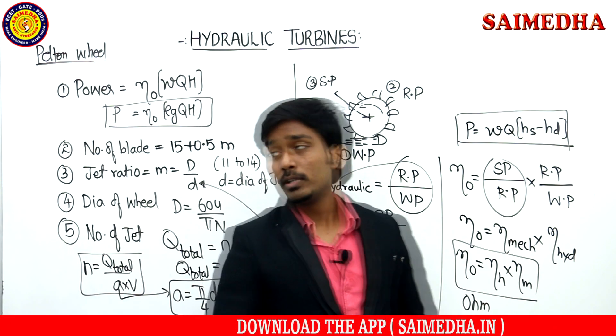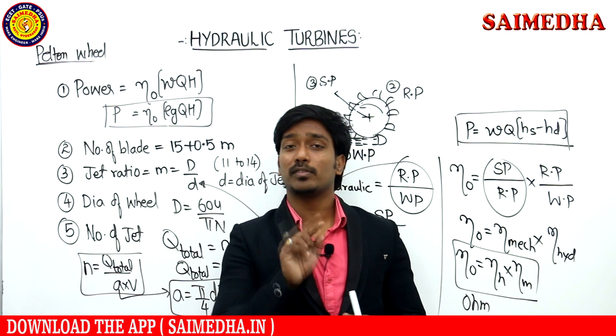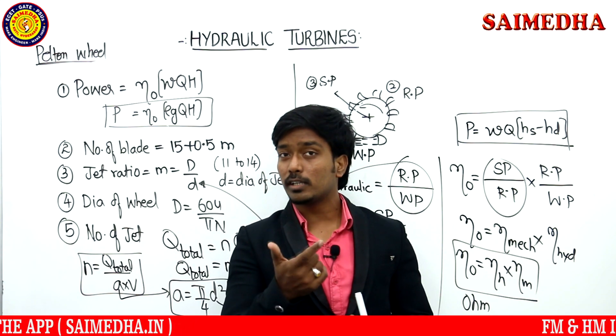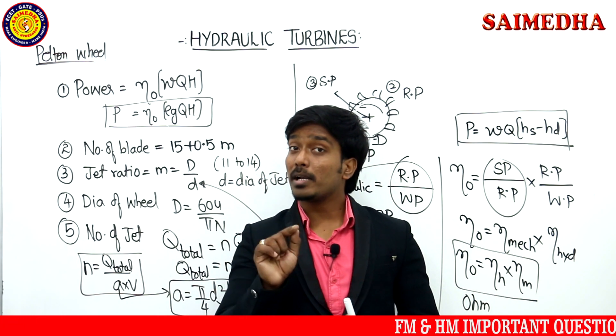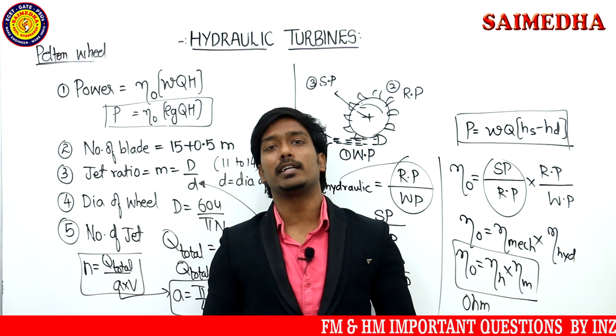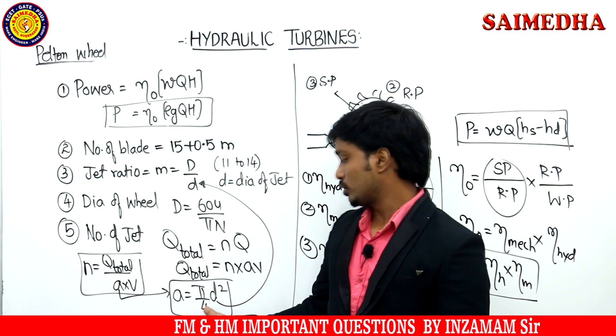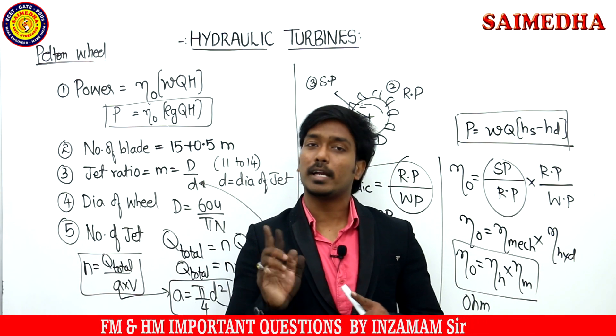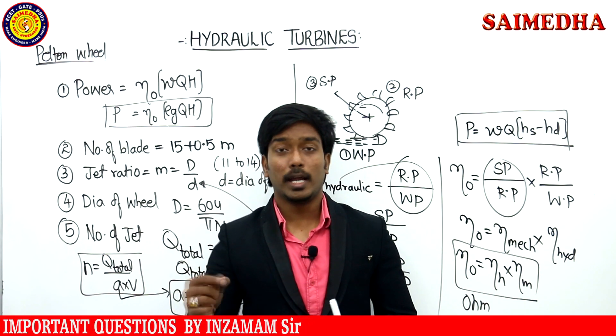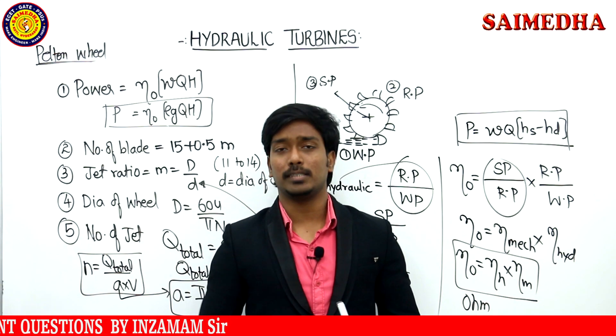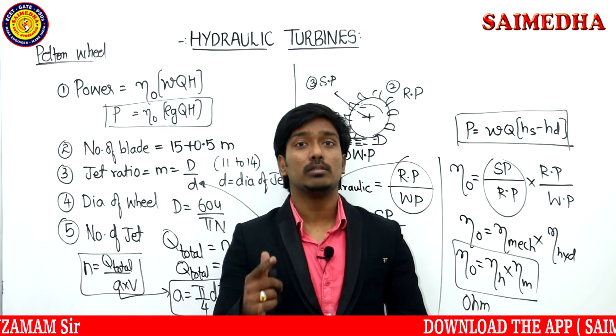Let's recap the formulas. First: Power = overall efficiency × ρ × g × Q × H. Second: Number of blades Z = 15 + 0.5 × M — this is an empirical formula. Jet ratio M = capital D / small d, value around 11 to 14. Capital D = 60U / πN. Small d = diameter of the jet. Area of jet = π/4 × d². Number of jets n = Q_total / (A × V). Three efficiencies: hydraulic, mechanical, and overall efficiency.